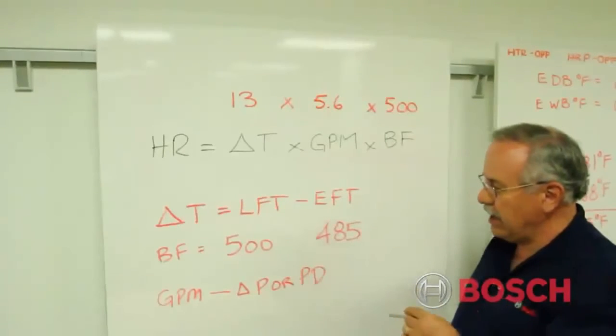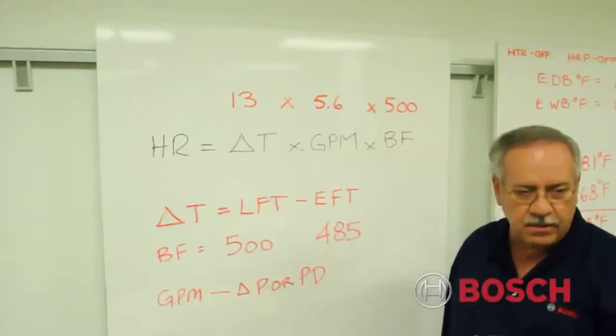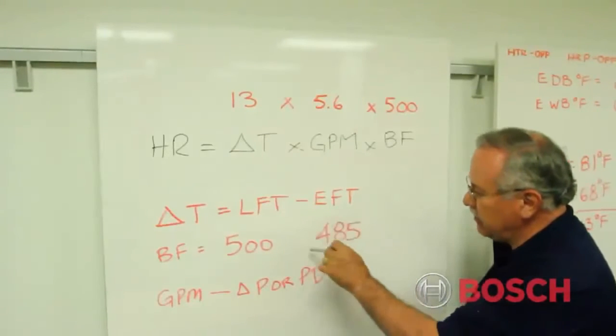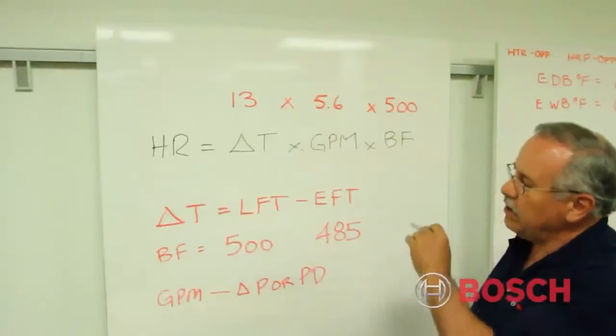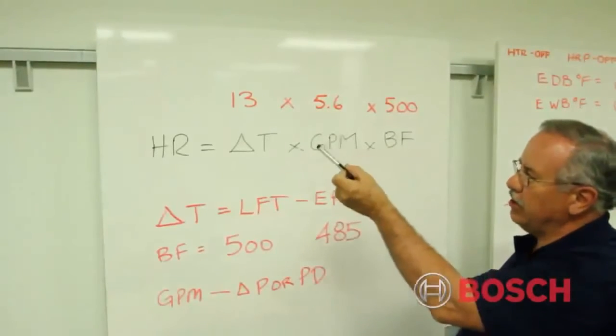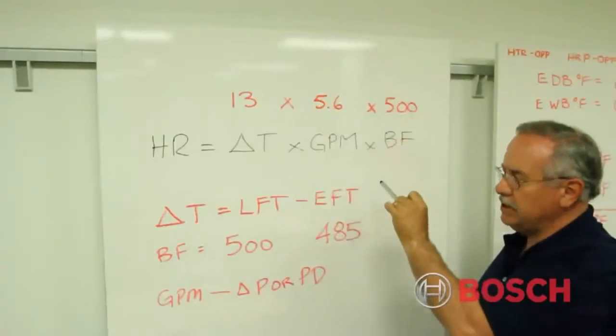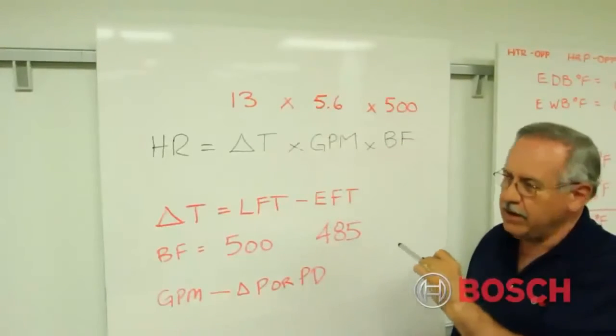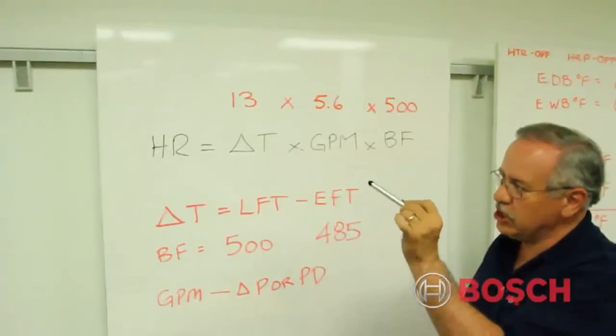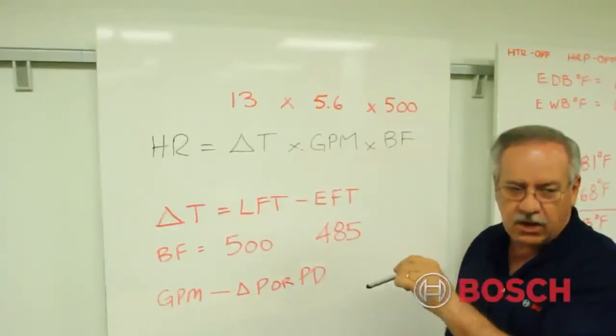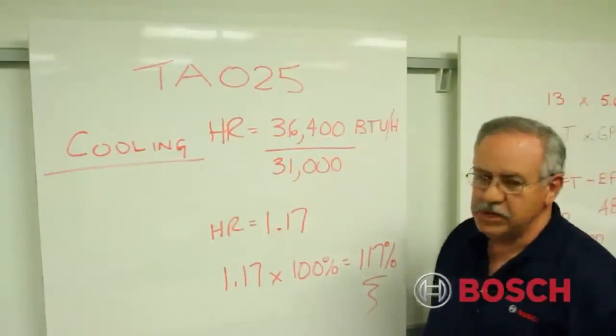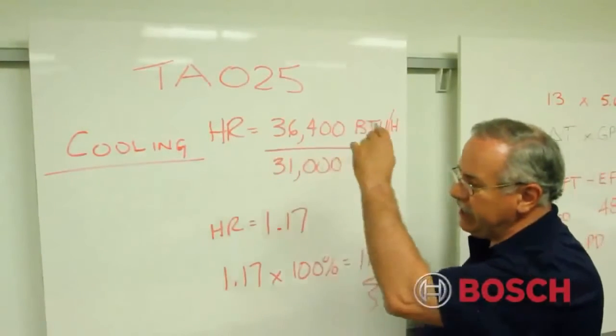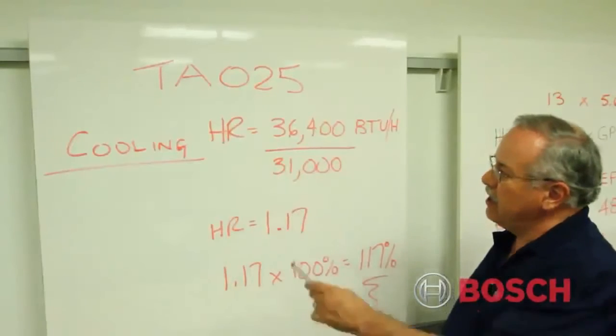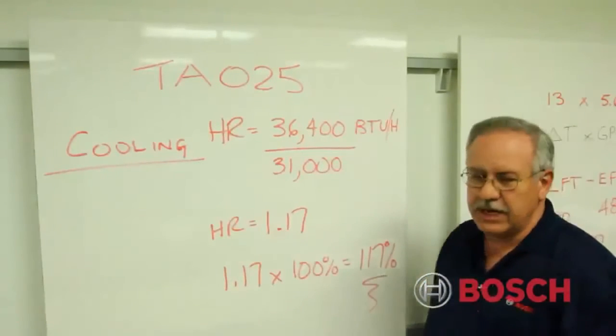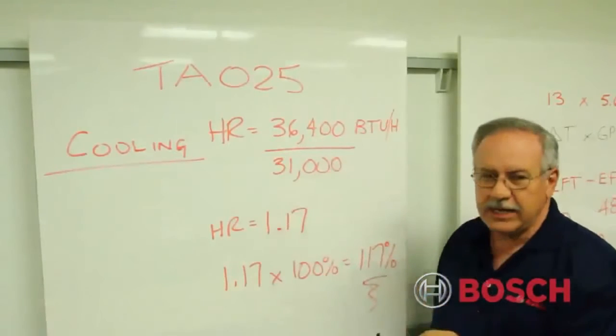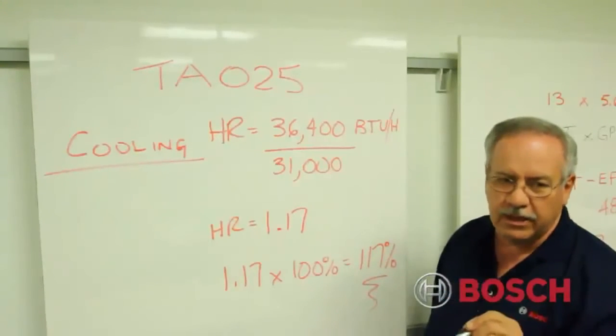If Mark had been using a glycol, antifreeze, methanol, or any other acceptable antifreeze solution with a closed loop, then he would have simply substituted 485 into the formula. So now we have all the factors to give us the answer, or 13 degrees delta T times 5.6 gallons per minute times the brine factor of 500 for this TA025 at these conditions to determine the heat of rejection into the earth. Now the final step in determining the heat of rejection in this particular case, remembering that we have a TA025 and we're operating in the cooling mode, what we have calculated is approximately 36,400 BTUs per hour is being rejected based on our conditions at this particular location.